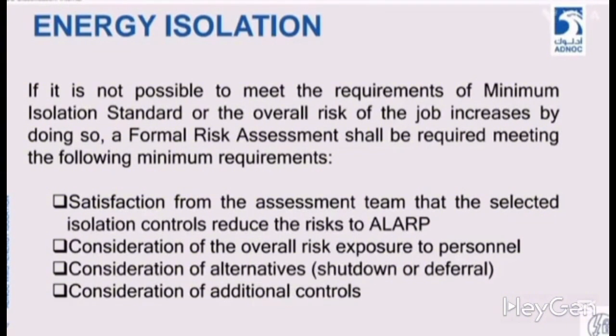The next and last point that we need to consider in the FRA is the consideration of additional control. If we had to close a supply valve somewhere and we are unable to properly isolate it from any region, we controlled the valve. If we are unable to apply mechanical isolation or double isolation, we can go and close their main control valve, which will ensure double isolation for us. For example, if we have a sulfur pit, we need to close all the service steam valves for it. If we are unable to close these valves here, we have closed the valve but cannot insert the blind, then we need to close the main control valve of the service steam. This will ensure that when our people are cleaning the sulfur pit, they are not in any way exposed to steam. We need to ensure double protection.